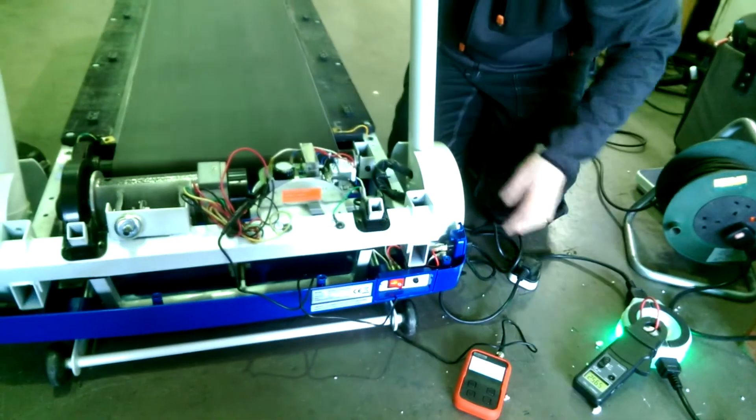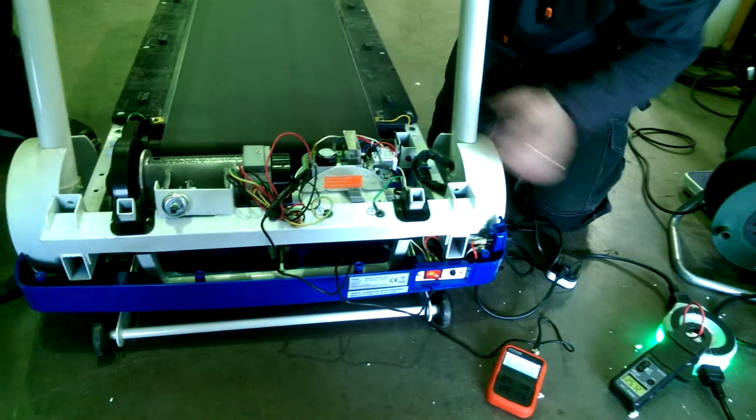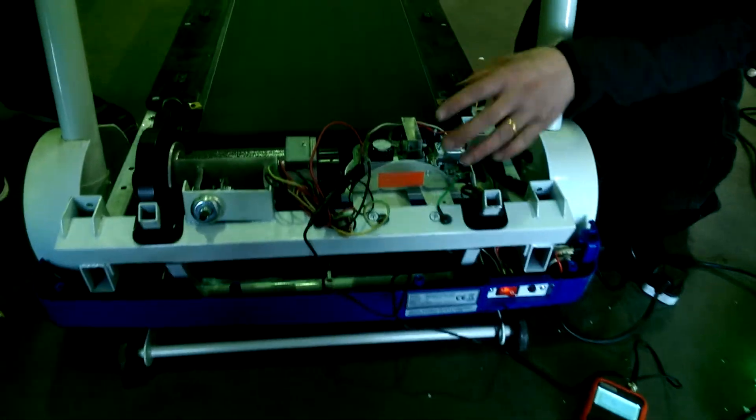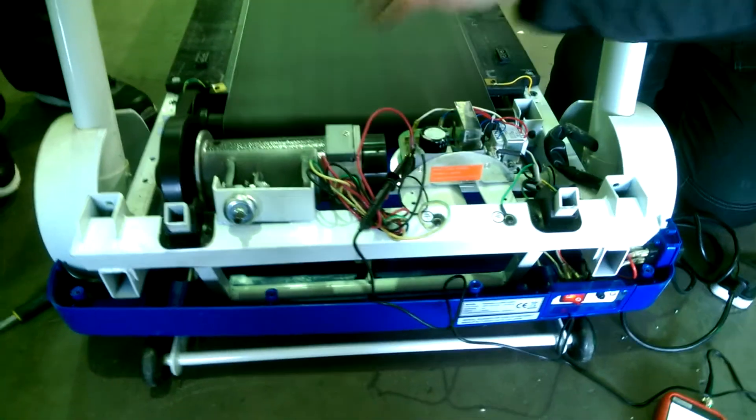So that's the pulse width modulated signal that's your DC which is driving the motor, and if you get a trace like that, well that's fine. So the MCB on this machine looks to be running okay. The current draw on the motor is running okay.